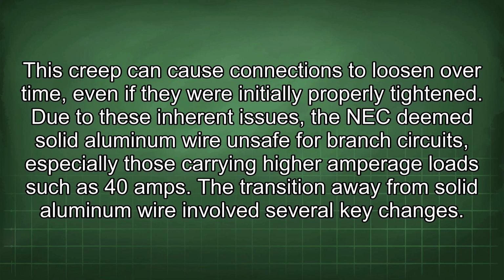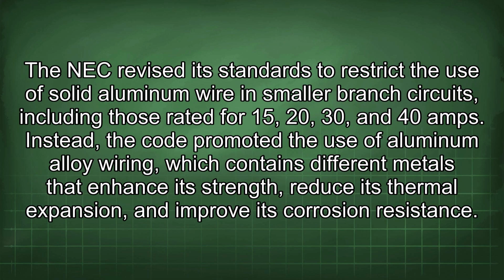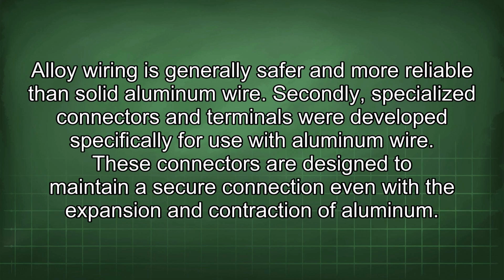The transition away from solid aluminum wire involves several key changes. The NEC revised its standards to restrict the use of solid aluminum wire in smaller branch circuits, including those rated for 15, 20, 30, and 40 amps. Instead, the code promoted the use of aluminum alloy wiring, which contains different metals that enhance its strength, reduce its thermal expansion, and improve its corrosion resistance. Alloy wiring is generally safer and more reliable than solid aluminum wire.